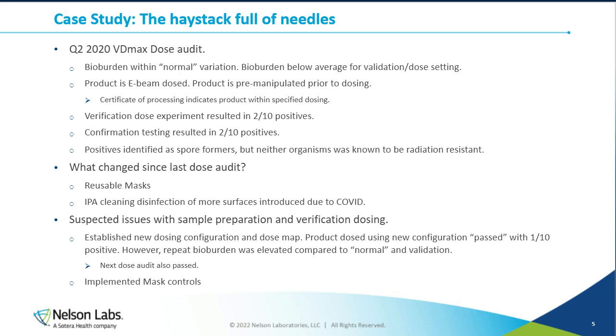So then when we did the test of sterility, we had 2 out of 10 positives. That triggers confirmation testing, which had an additional 2 out of 10 positives, indicating we had a failure of the dose audit. Now, 2 out of 10 both times shows that we're actually really close. We've just moved out of basically our sterility assurance level. We've just had that bit of an increase that's pushed us out of being able to have our sterility assurance level.